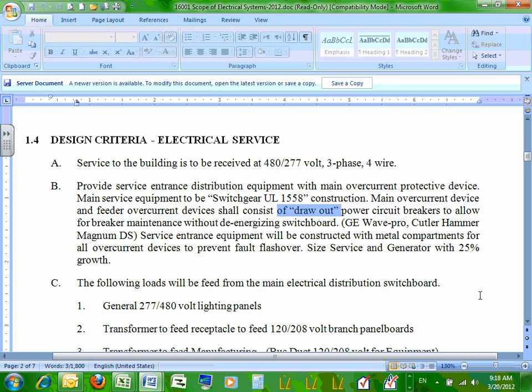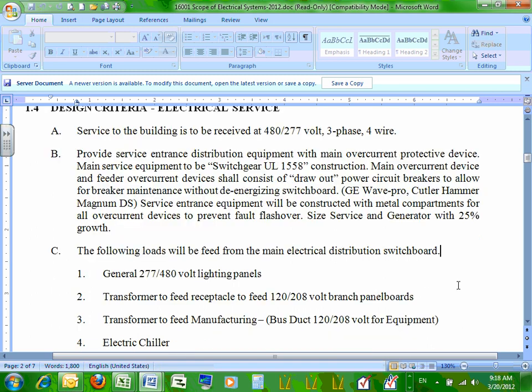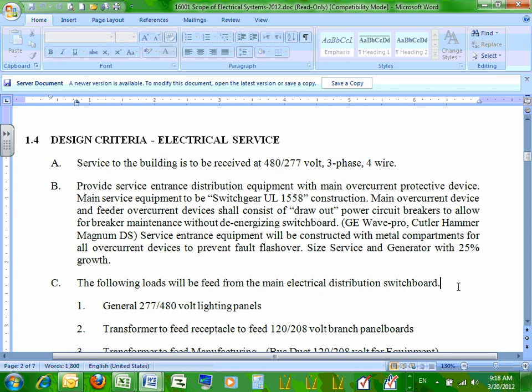And so it simplifies maintenance or repair if there's a problem at that switchboard. It's more expensive, takes more room, but in an industrial setting and even in our data center settings, that's what we're requiring for speed of repair, replacement, speed of maintenance, and speed of recovery if there is a failure. So I'm requiring that. Something to think about.